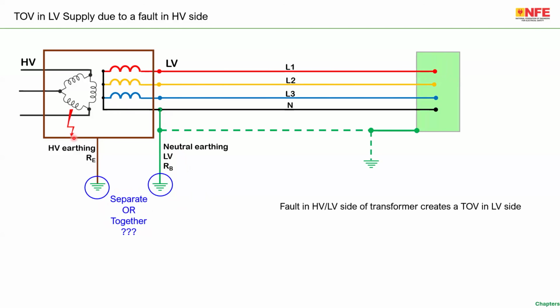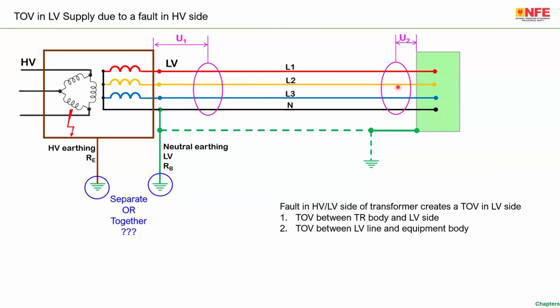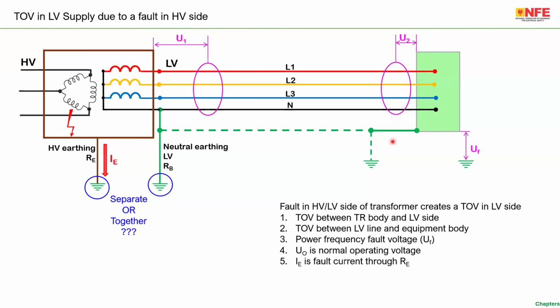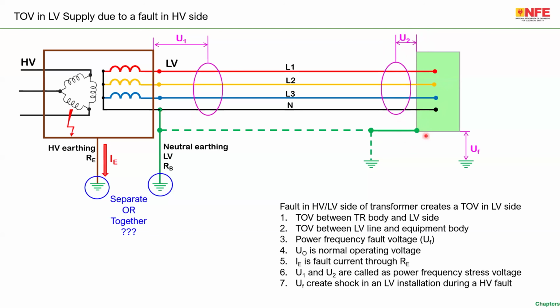Now a fault on the HV side of the transformer can create three problems in your installation. A HT fault creates a voltage stress on the LT side of the transformer, and a voltage stress on the connected equipment. Example, 100 refrigerators in 50 houses burned, LED TVs in 25 houses burned. These are due to the transferred potential or stress potential U2. And the third one is a person who is touching any metallic object at the consumer premise. For example, here the person may get a shock during a fault on the high voltage side of the transformer. So basically, a fault on the high voltage side of the transformer is also creating multiple problems on the low voltage side of the transformer.